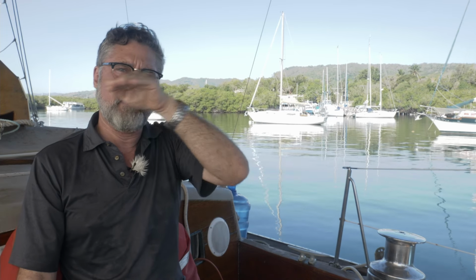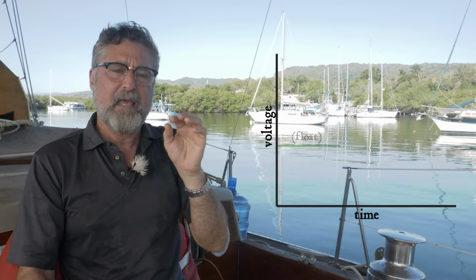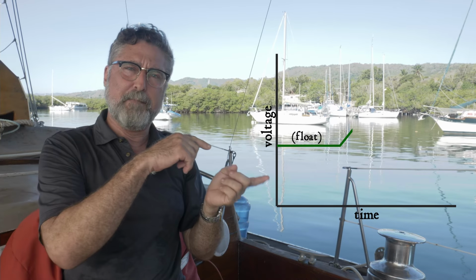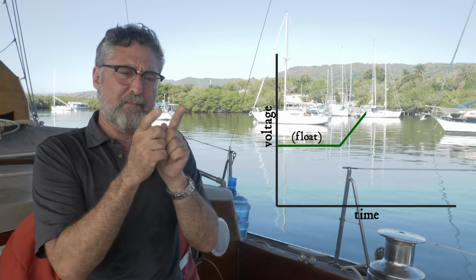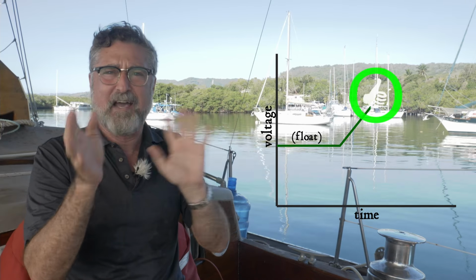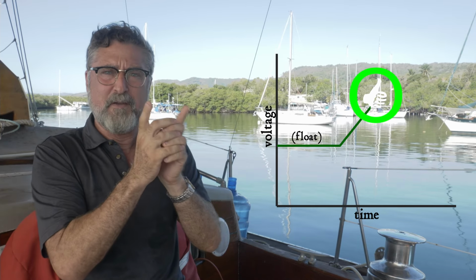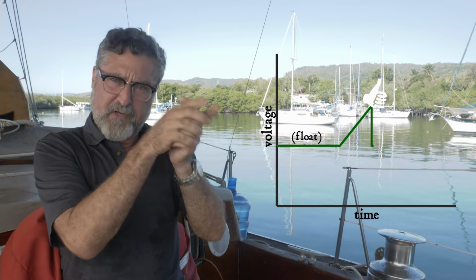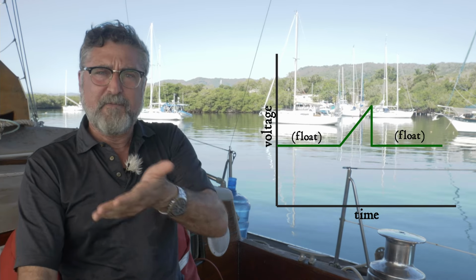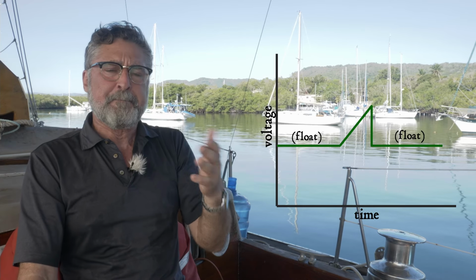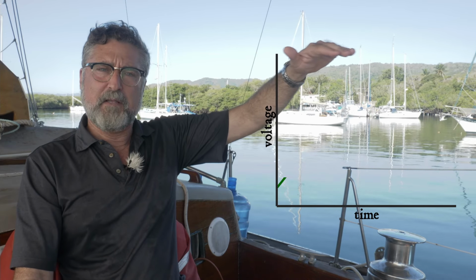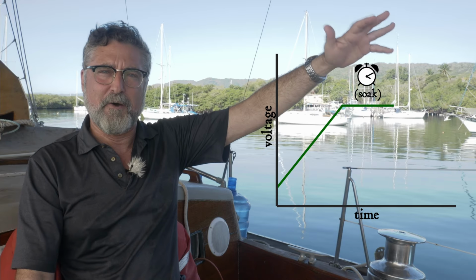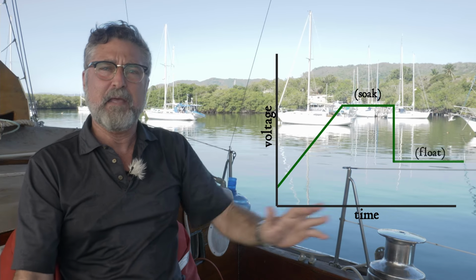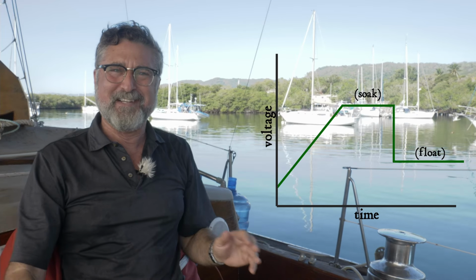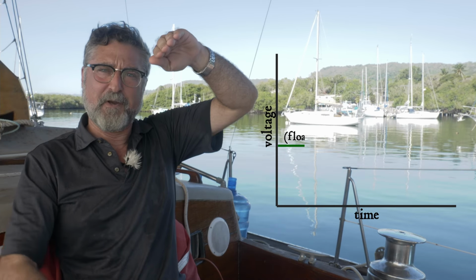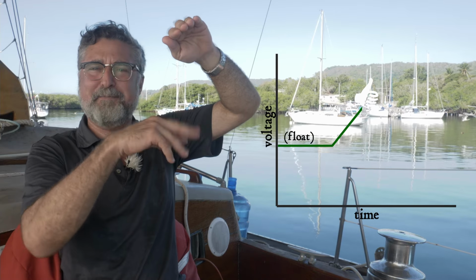The right trigger to say when to come out of that high voltage state is to watch the amps going into the battery — when it's only accepting a certain percentage of its size, a known number, shut down at that point. So with my earlier example, the first time it might stay maybe 3 hours if the batteries were low, but eventually they'd be fully charged and it would come down. If you restarted the engine, it would come up to voltage very quickly since they're already fully charged, and say, oh, this battery's already full.